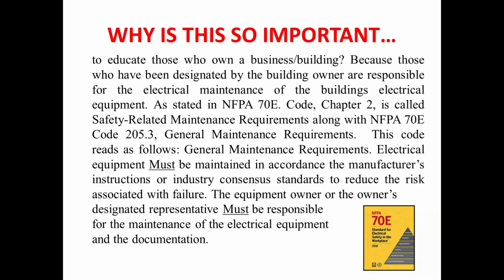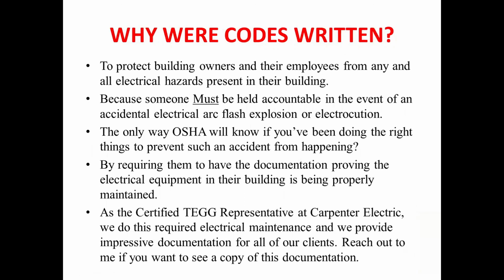The equipment owner or the owner's designated representative must be responsible for the maintenance of the electrical equipment and the documentation. That documentation is extremely important for protecting building owners and their employees from electrical hazards, because someone must be held accountable in the event of an accidental electrical arc flash, explosion, or electrocution. The only way OSHA will know you've done the right thing to prevent such an accident is by requiring documentation that the electrical equipment in the building is being properly maintained.